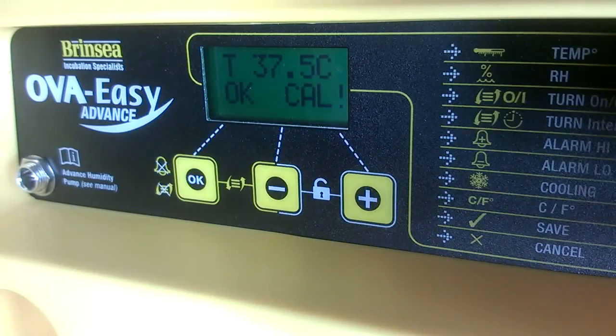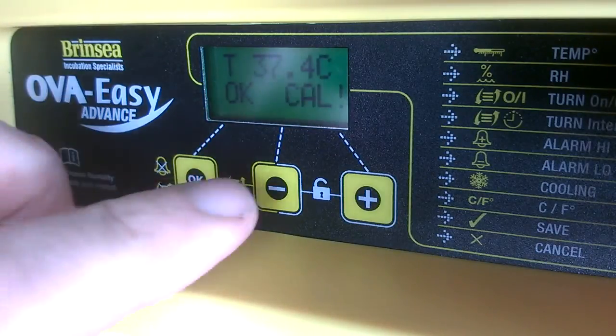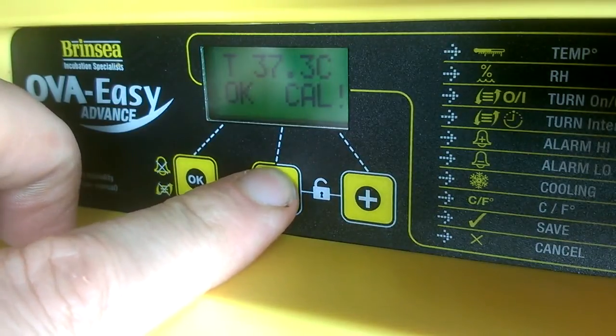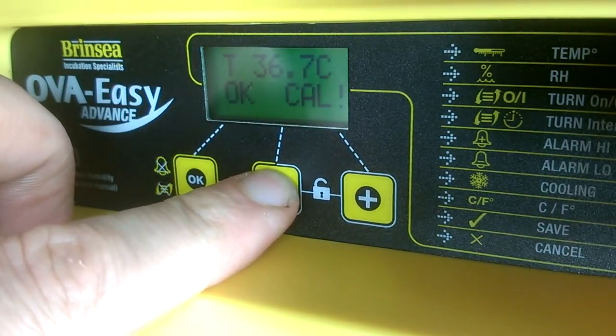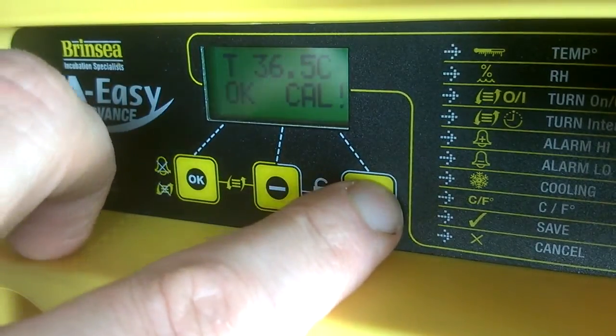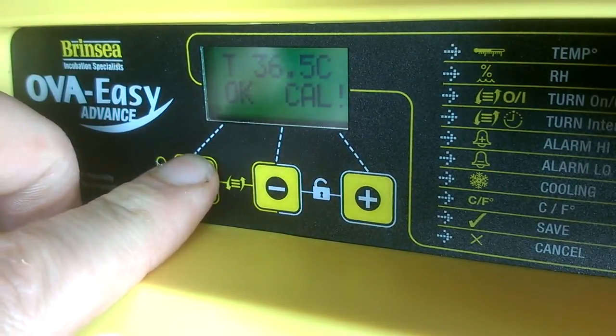Let's assume that on the thermometer that we're using to calibrate, we're reading a whole degree lower. Let's say we are reading 36.5 on the thermometer in the machine. So from this point in the calibration menu, we can reduce the temperature that the machine is reading so that it matches the temperature on the thermometer. So let's do that. We're going to use the minus button to reduce that temperature till we get to 36.5. 36.6, 36.5. We're going to go OK to that.